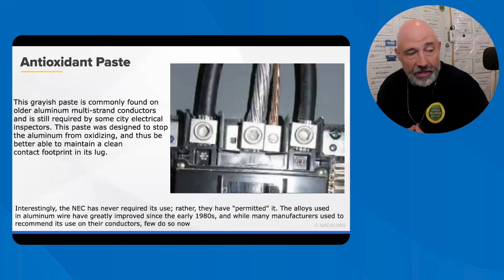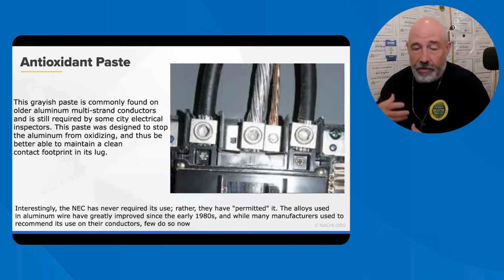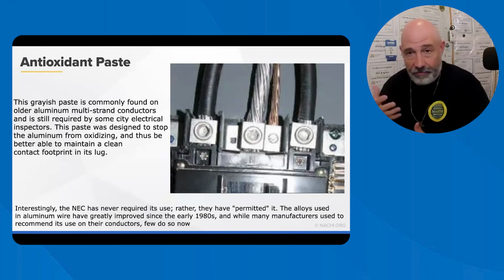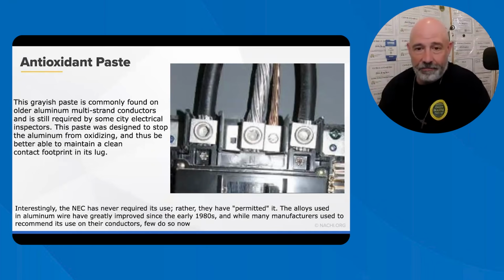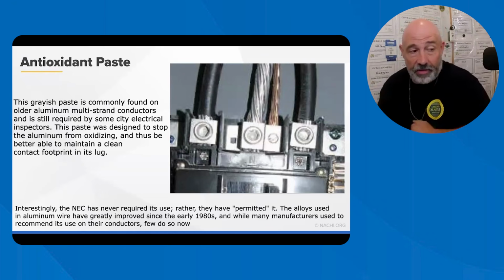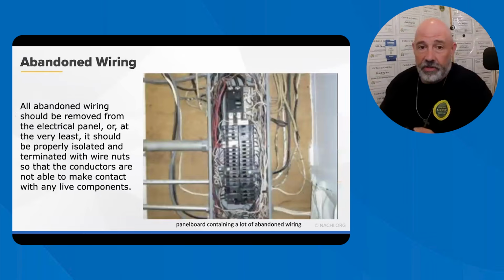Oxidation paste, you're going to see this quite a bit on your panels. They put this paste on there to help with the oxidization. It's never really required, but you'll see it quite a bit, and it is permitted. It allows the aluminum wire to have better conductivity, and it doesn't oxidize as fast.